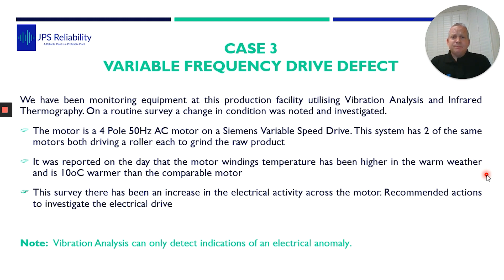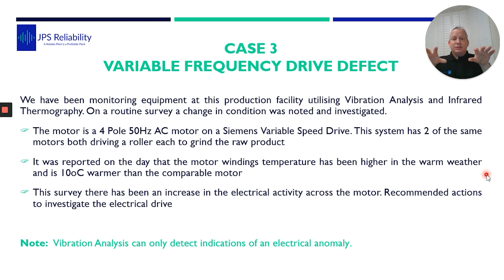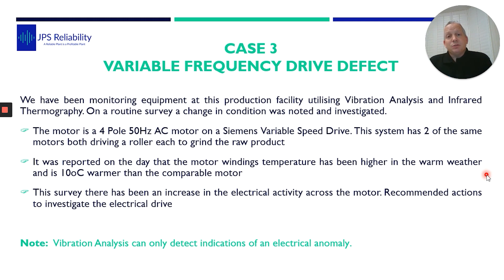So this is a four-pole motor, 1500 RPM, at 50 hertz line frequency. It's two motors driving two epicyclic gearboxes, in turn driving two rollers crushing the product. They're both under the same torque, tension, load, and stress. On the survey, we noticed this difference in vibration analysis and then through thermography as well. From that, we decided to alert the plant electrical engineer and advised a full electrical inspection prior to any failure.